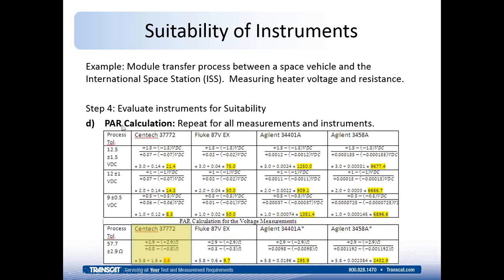So you repeat that process accuracy ratio or PAR calculation for each of the different measurements, each of the different process tolerances versus each of the instruments you're considering, and you come up with those ratios. And you can see from this chart, and when you look at the Agilent 3458, these are almost 10,000 to 1, 7,000 to 1, 2,500 to 1. They're very, very large. And so that's definitely overkill for that measurement. It'll make the measurement, no doubt. When you get to the other end of the scale, when you're looking at the Centech model, you have a 21.4-to-1 ratio, 14.3 to 1, 8.3, and then this 3.6 to 1 that we calculated for resistance. So that one's below 4 to 1, and that may be a concern, or maybe not. Depends on the application and how much risk you want to take. And now, in the rest of this webinar, I'll be defining how much risk is too much risk.